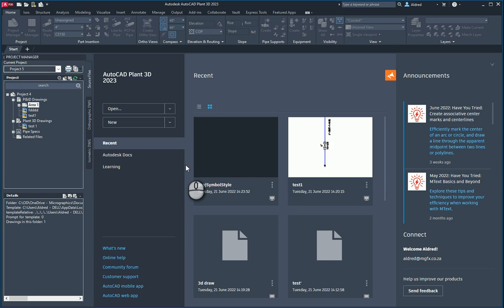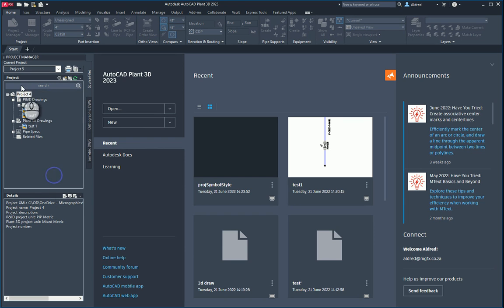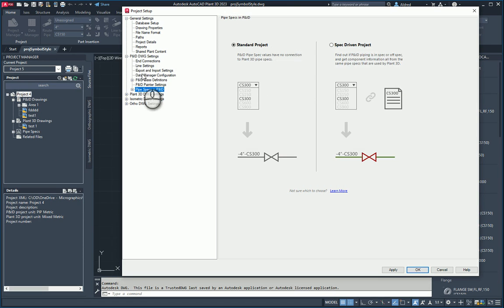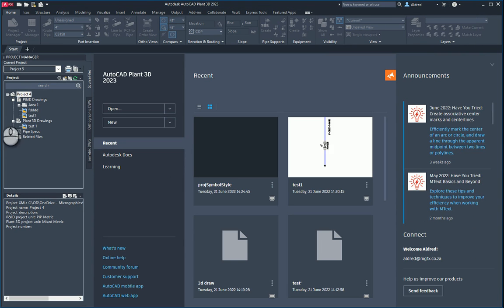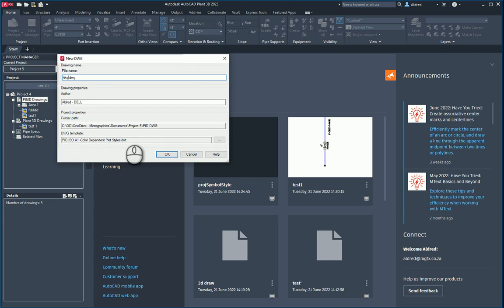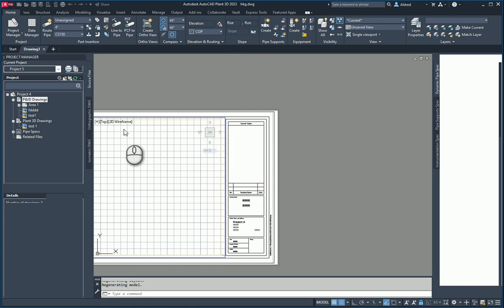In our project setup, we can actually set AutoCAD Plant to look at the specs when we're drawing our P&ID. I'm going to go to my project setup, and under P&ID DWG settings — pipe specs and P&ID — you'll see the default is standard project. I'm going to make it spec-driven. This allows us to more easily sync up the specs we're using in AutoCAD P&ID with our AutoCAD Plant as well.